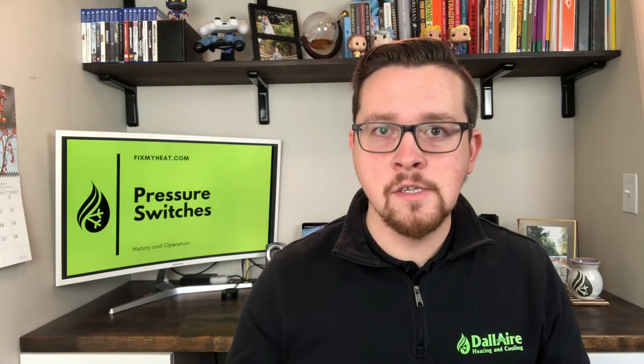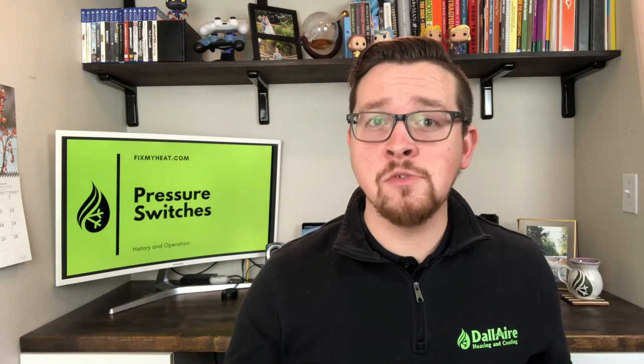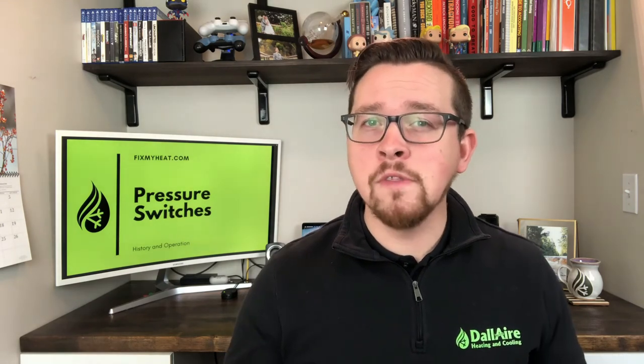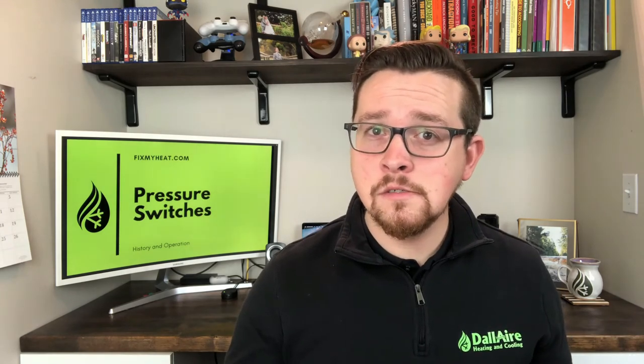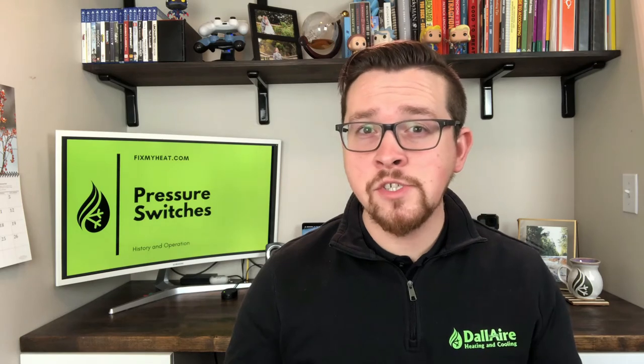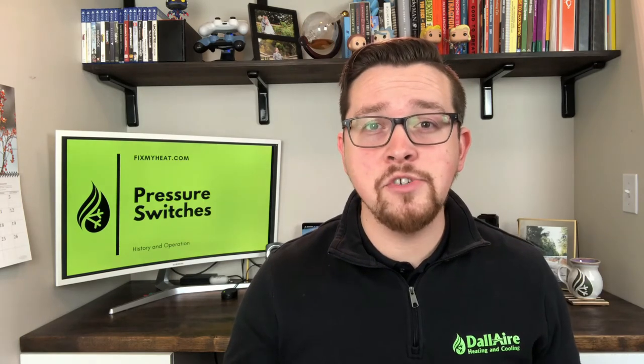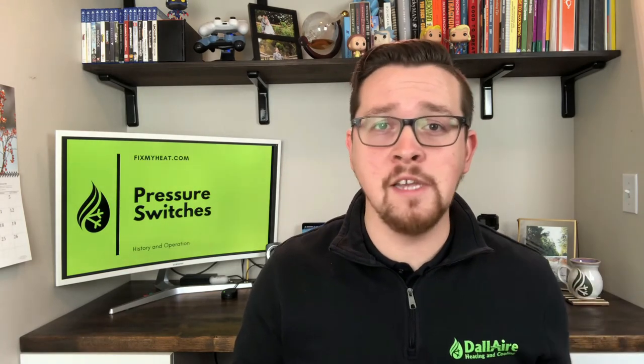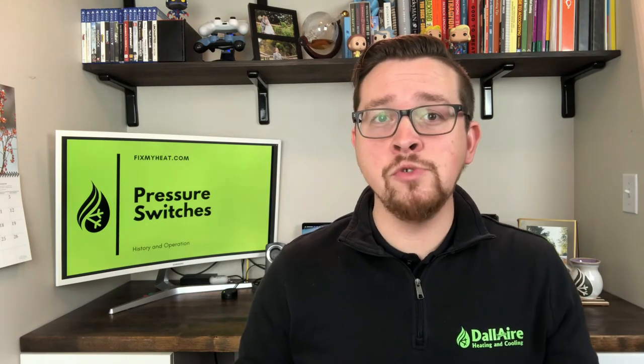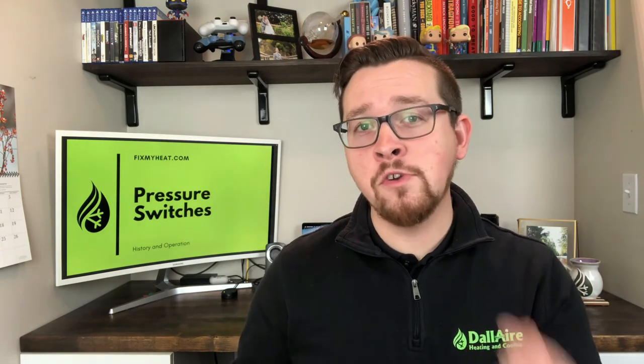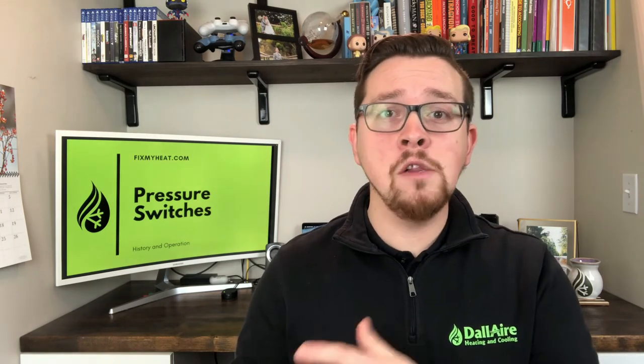I could give you an unlimited amount of examples and experiences that I've had over the past 15 years, but every service call with a potential pressure switch issue is circumstantial. And it's more important that you comprehend what's happening with the mechanics of the furnace so that you can eliminate the possibility of a vent restriction, a plug drain, a plug secondary heat exchanger before replacing the pressure switch. This applies to all diagnoses. Find out what the overarching issue is with the system before replacing any parts, because a part might be failing due to the improper setting of another part. You want to do your due diligence as a technician to make sure that all of the system is operating properly, that you're not just fixing today's issue, but possibly the issue that's causing today's issue.